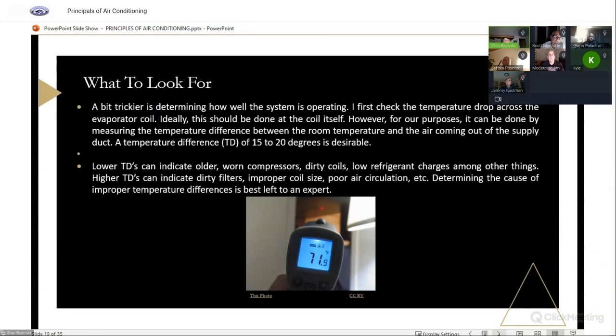A little bit trickier than looking at the physical condition of ductwork and A-coils and drip pans and the condensing unit is determining how well the system is actually operating. So it's running, it's 81 degrees outside, the house feels cool. I check the temperature drop between the supply air and the room air. Normally you want to take it across the coil, but we're not going to do that. So I just use the supply air into the room and the room air and get an idea of where we are. It should be 15 to 20 degrees differential.